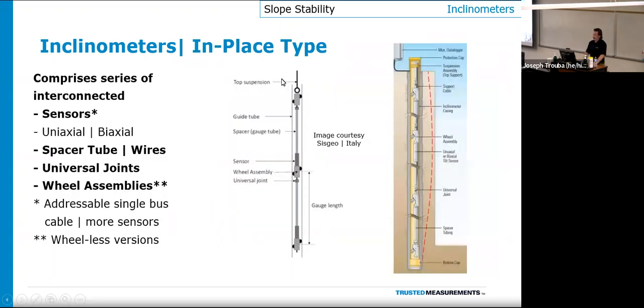So now, taking it a step further, we'll get into in-place inclinometers. Same type of measurement, except this instrument sits in the casing permanently or semi-permanently, so basically for the duration of measurement. These can typically be reused, reconfigured in a different project or a different hole. But for all intents and purposes, they're left in the hole for long-term measurement or the duration of your monitoring program.